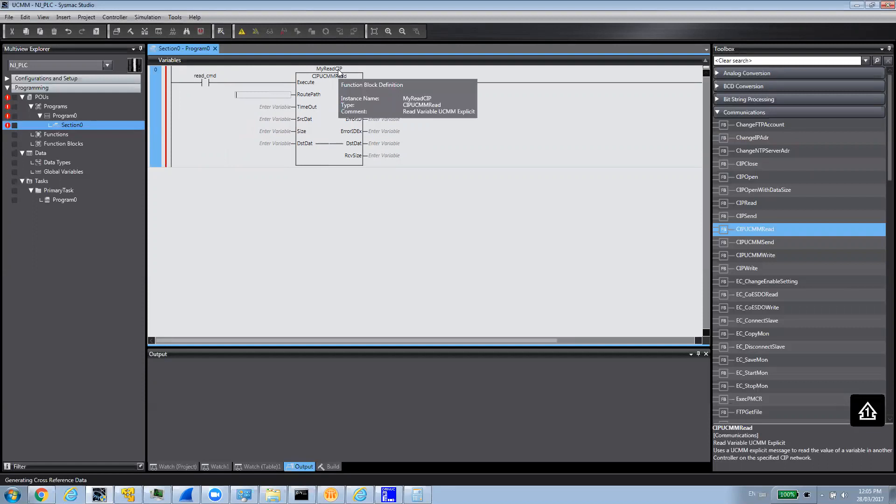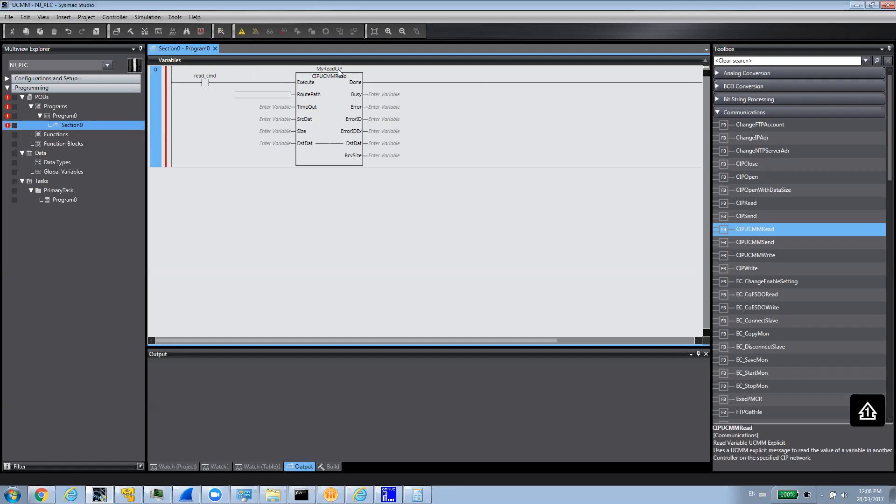And then, I have to specify the route path. Now, in my case, as we saw, the IP address is 192.168.250.100. The way to specify the route path is we have to specify the port first that Ethernet IP scan use. Typically, it's port 2. Sometimes, depending on the device you deal with, it might be different. But typically, it should be port 2. I'm going to specify the IP address: 192.168.250.100. This is a string variable, and that's why I have these symbols in here. But I could put also just like a variable and dynamically change this if I want. I could put a string variable and change it if I want, but I don't need to for the purpose of this demo.